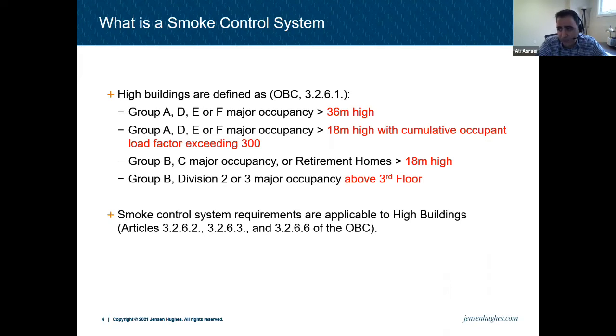Group B and C major occupancy over 18 meters automatically, or a retirement home actually as well, over 18 meters, it's a high building. If you have Group B, Division 2 or 3 major occupancy above the third floor, again, it's considered a high building. And if it is a high building, we are dealing with the requirements for the smoke control system, which are applicable based on Articles 3.2.6.2, 3.2.6.3, and 3.2.6.6 of the OBC.